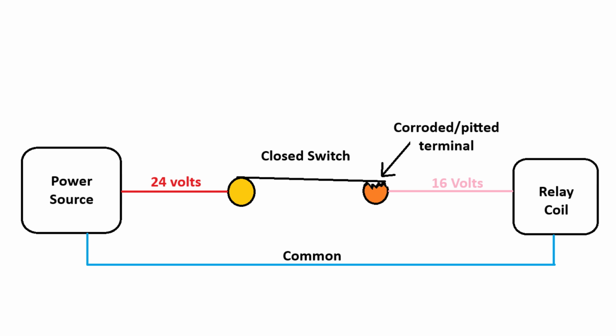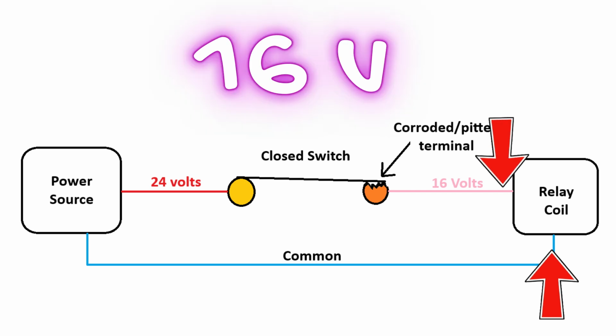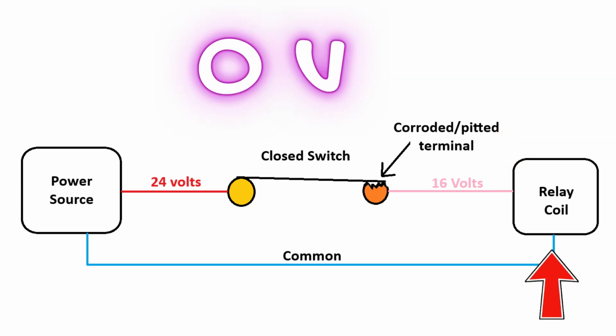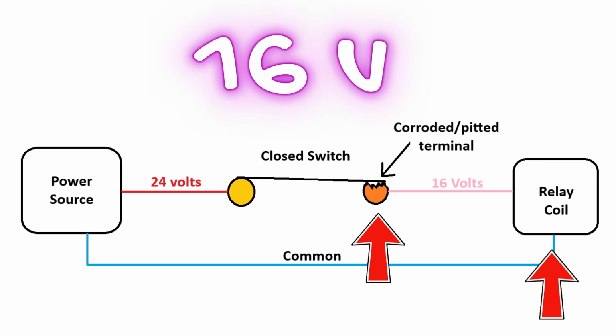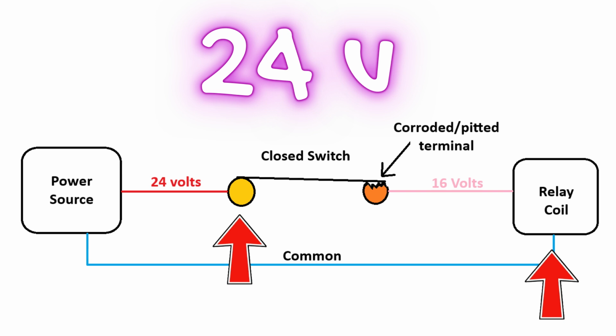So in order to weed out these kinds of problems, once you confirm you have a voltage drop, basically all you want to do is hopscotch backwards from that point and see where that drop is actually occurring. So in this example, let's say I put one of my probes at the relay coil, the other probe on the other side of the relay coil, and I'm only reading 16 volts. At this point, I can go backwards to the terminal on that closed switch, reference common, and see what my voltage there is. Now, if I go to the hot side of that switch and I'm reading 24, then I know I'm experiencing a voltage drop there across that closed switch.